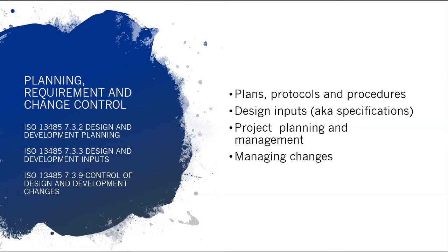So just to be clear, it's not a design and planning document for the management of the project. It's for the management of the design controls. Well, it does incorporate project management aspects, but it's not in the form of a Gantt chart or a timeline. It is a document that prescribes the steps to be followed and the documentation to be generated along the way. And there are some quite specific requirements in those sections of ISO 13485 that define what needs to be included. It's beyond the scope of what we can talk about today to get into the dirty detail of that, but it is quite complex.